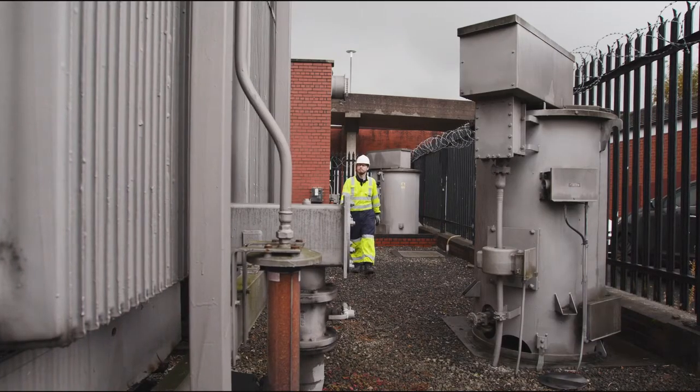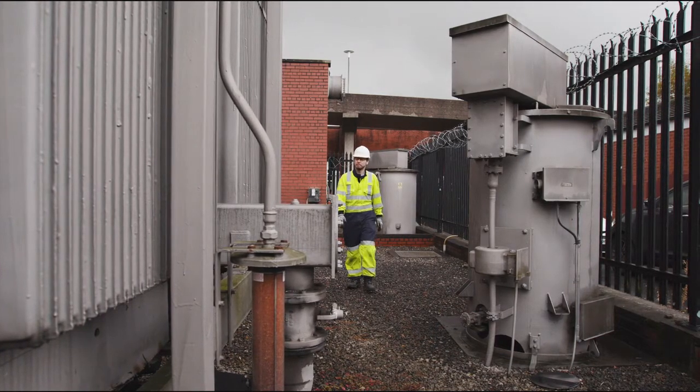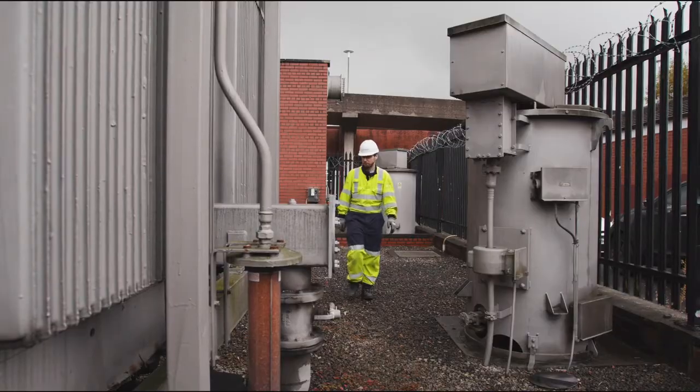So far we've deployed Class in 250 of our primary substations, out of a total of just over 300 substations across our entire network. So it's quite a significant deployment, reaching over 1.7 million of our customers in total. In essence, Class is advanced transformer tap changing technologies, which we've upgraded across those substations, and then integrated back to our network management system, which is an advanced platform which enables us to quickly and with minimal impact on customers elicit a significant demand response.